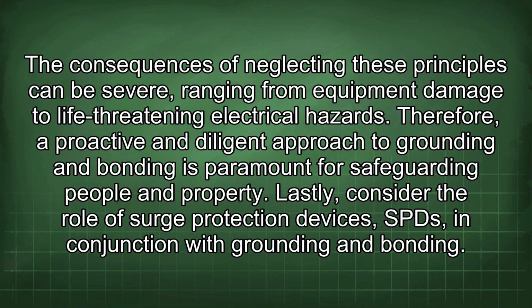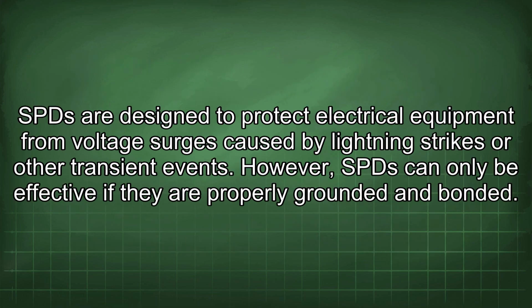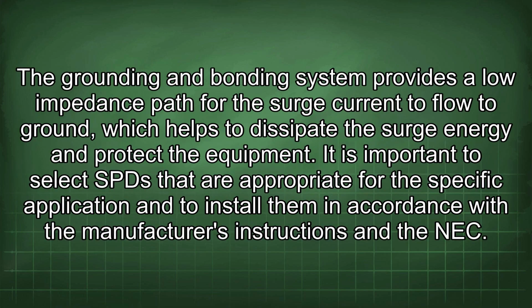Lastly, consider the role of surge protection devices, SPDs, in conjunction with grounding and bonding. SPDs are designed to protect electrical equipment from voltage surges caused by lightning strikes or other transient events. However, SPDs can only be effective if they are properly grounded and bonded. The grounding and bonding system provides a low impedance path for the surge current to flow to ground, which helps to dissipate the surge energy and protect the equipment. It is important to select SPDs that are appropriate for the specific application and to install them in accordance with the manufacturer's instructions and the NEC.